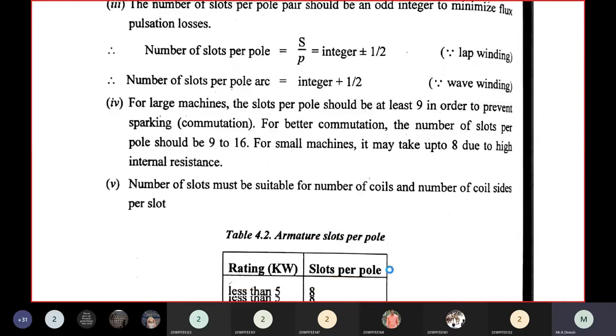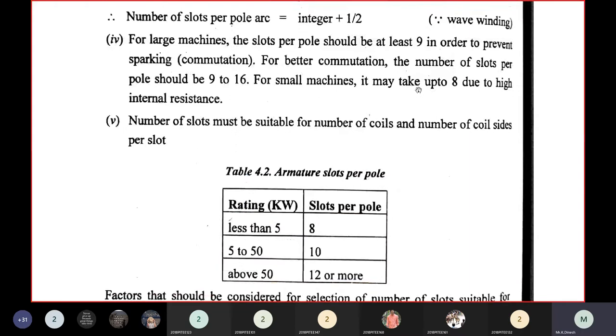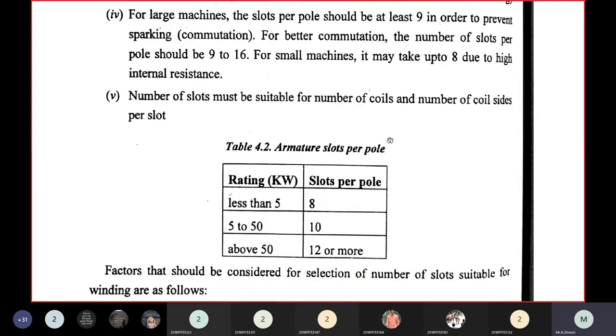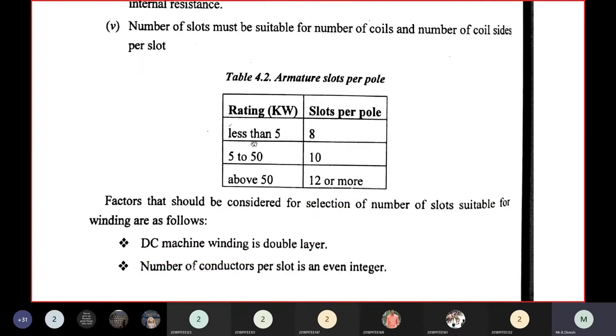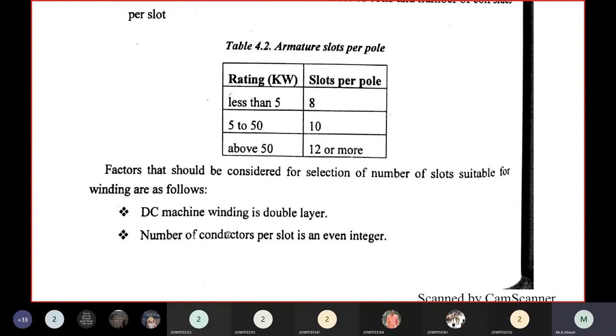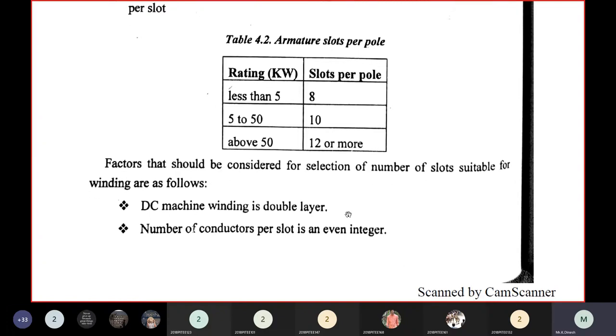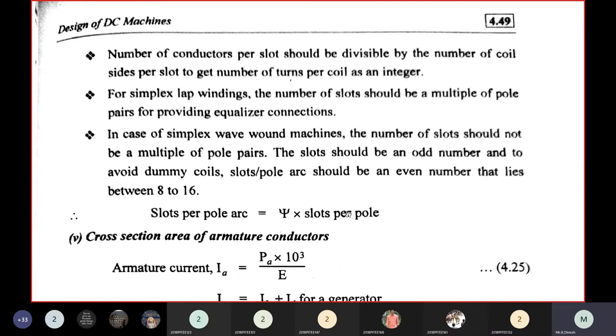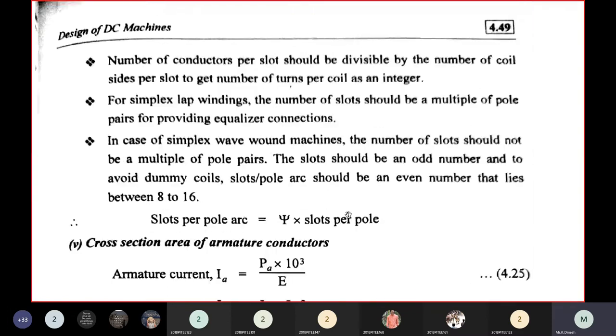The fifth guideline: the number of slots must be suitable for the number of coils and coil sides per slot. For less than 5 kW, use 8; for 5 to 50 kW, use 10; above 50 kW, use 12 or more. DC machine winding is double layer, and the number of conductors per slot should be an even integer, divisible by the number of coil sides per slot to get an integer number of turns per coil.